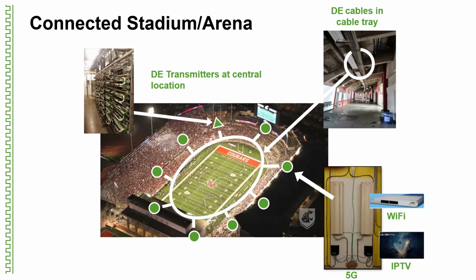Here's a stadium application. The main thing is the transmitters range anywhere between 100 kilowatts and 2 megawatts in these installations. We have rooms with digital electricity transmitters in a central location, and power can travel as far as 2 kilometers from those transmitter locations. The advantage is it uses the cable tray underneath the seats, carrying our power as well as data lines. That's another example of convergence—very rapid to install and low cost versus hard conduit runs through a building.